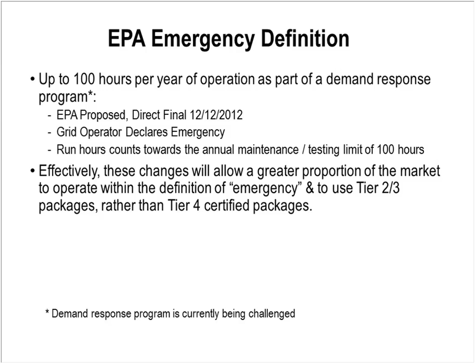We receive a lot of questions about the different classifications of engines, both emergency and non-emergency, so I'd like to summarize the practical differences between emergency and Tier 4 certified, or non-emergency, engines. Starting on the left, we have the stationary emergency engines just discussed, which are effectively Tier 2 and Tier 3 certified, carrying that basic stationary emergency certification and legal only for emergency applications—usable for up to 100 hours a year of maintenance and testing, 50 hours a year of general use out of that 100, but unlimited use during an actual emergency situation.